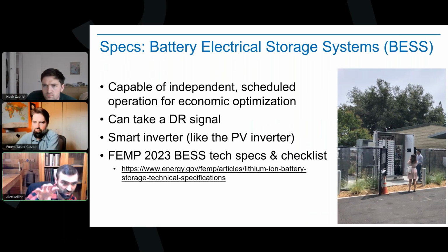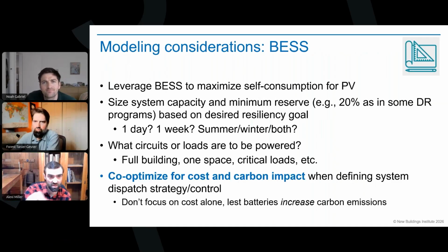When we're talking about doing it with storage, we want to make sure the storage systems can, as I like to say, take a signal and do something with it. We've got smart inverters, and we're co-optimizing for cost and carbon, thinking about what the system dispatch strategy is that we're modeling. Like I said at the beginning, what is the priority? What circuits are powered? What's the system size, and how much reserve do we keep? Some demand response programs that call on batteries say we're going to leave you the last 20% of your battery all the time in case you need it. Sometimes you might set that reserve higher. That impacts the functional size of the system, because if you never want to go below 20%, you need to know how much you have in your upper portion.